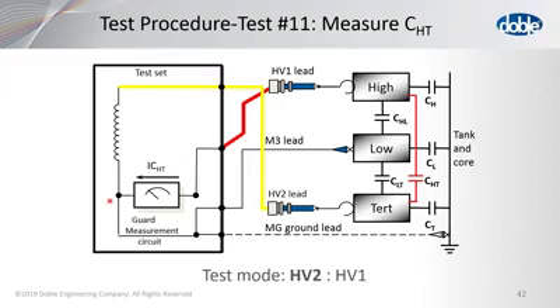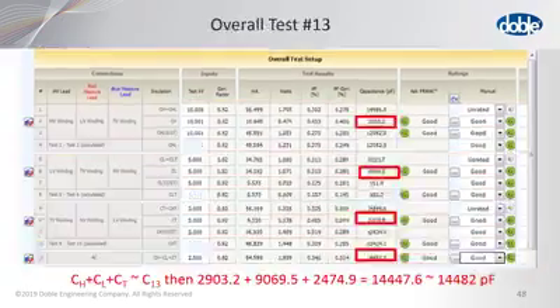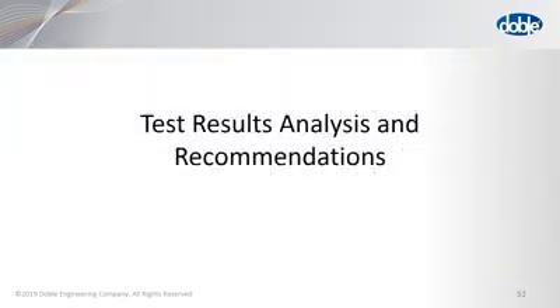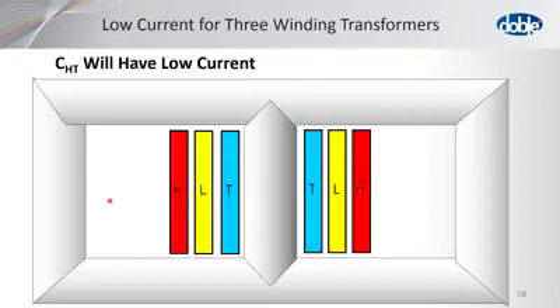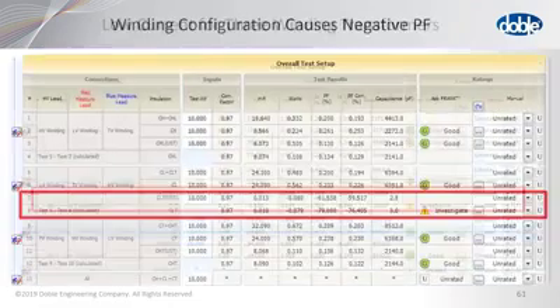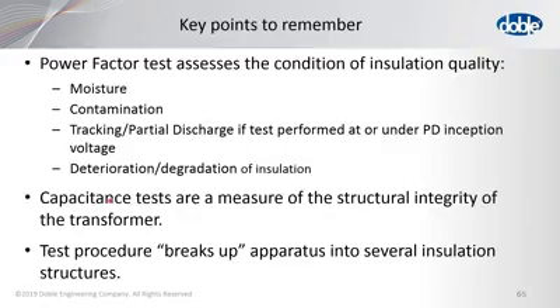Very good. Next question, Norbert. How would the bushing influence the UST current when testing between the high side and low side windings? Very good question. Very good question. I pointed out, and it maybe was not very clear when you first saw it, is notice that in the insulation, I went the wrong way.